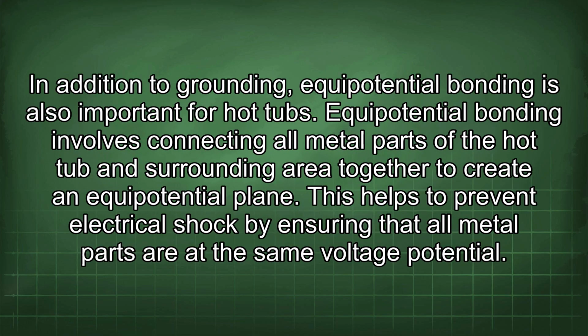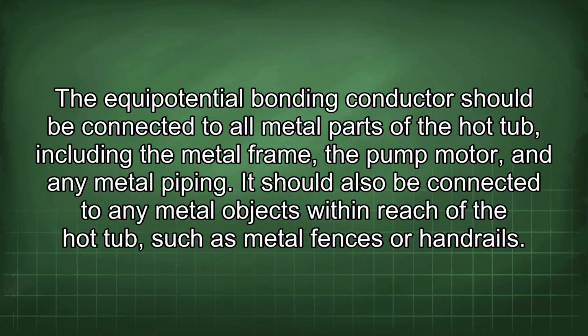In addition to grounding, equipotential bonding is also important for hot tubs. Equipotential bonding involves connecting all metal parts of the hot tub and surrounding area together to create an equipotential plane. This helps to prevent electrical shock by ensuring that all metal parts are at the same voltage potential. The equipotential bonding conductor should be connected to all metal parts of the hot tub, including the metal frame, the pump motor, and any metal piping.